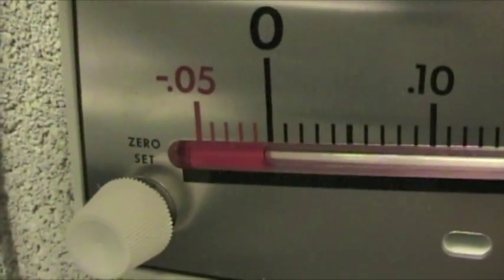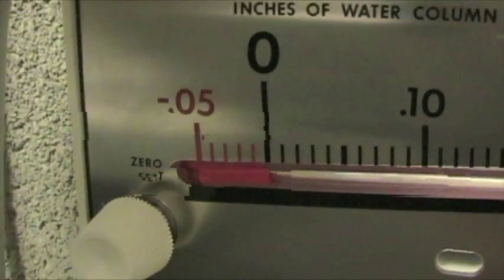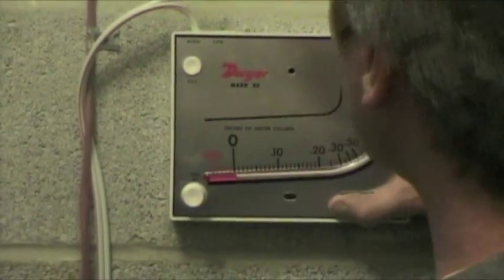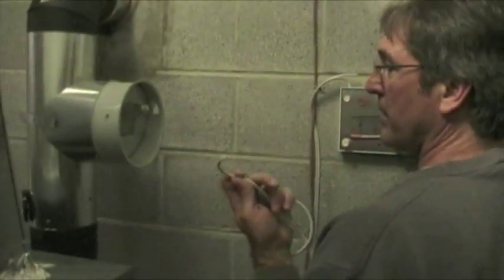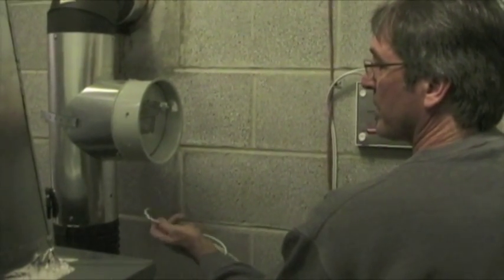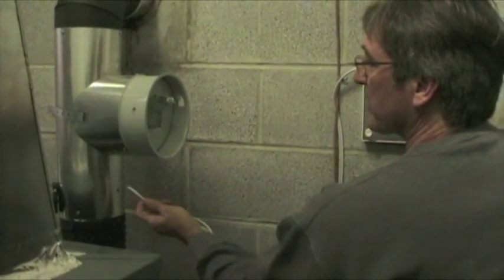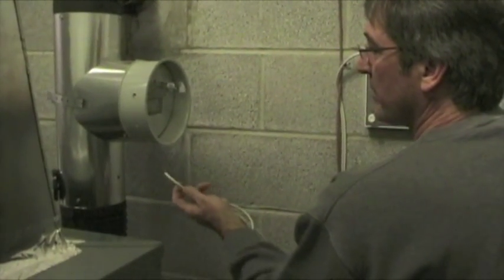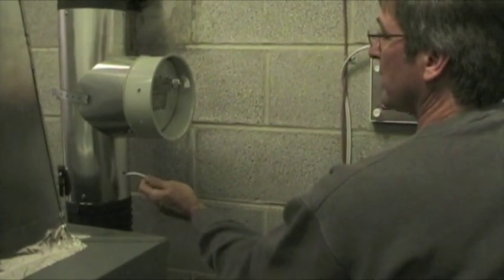I'm gonna put the tubing into the draft and see what we get. Meniscus is on zero. I'm gonna insert the rubber tubing into the flue proximal to the barometric draft regulator, between the BDR and the furnace, and measure the pressure.